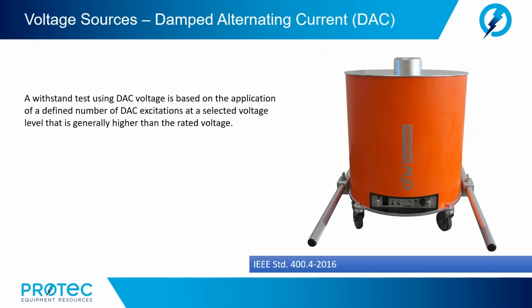Now, a withstand test using DAC voltage is based on the application of a defined number of DAC excitations at a selected voltage level that is generally higher than the rated voltage. DAC testing can be applied to all cable and accessory types, and it is based on the insulation breakdown, no breakdown outcome. In conducting a non-monitored withstand test, however, no information is gained about the test's effect on the insulation system.